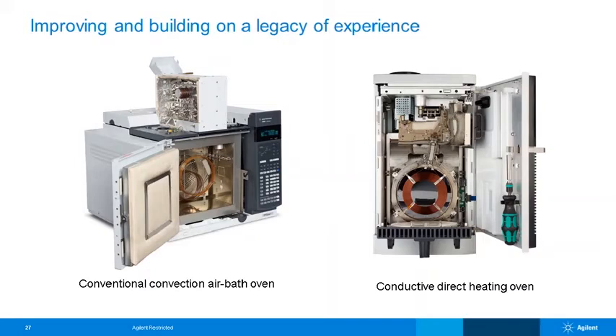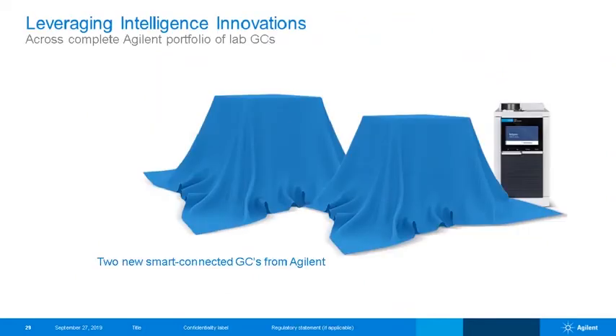So, if you wanted to develop a new air bath oven, because ultimately some people need the flexibility of an air bath oven, and the Intuvo would not be the right GC for everybody, where do we start? Well, we don't want to sacrifice the performance of the 7890 as far as repeatable heating is concerned. That oven is well recognized out there as giving excellent repeatable heating, as shown by the retention time stability that all our users are getting. But we also don't want to lose all of the intelligence and all the leak checking of the Intuvo. So if we combine the two in your mind, this is where we end up as far as the 8860 and 8890 are concerned, which are clearly those two blue sheets there.